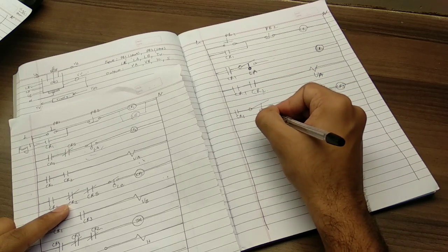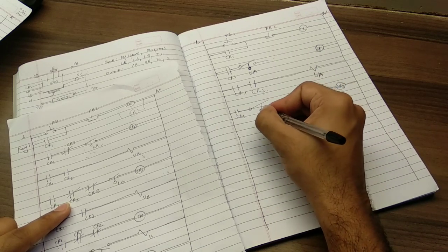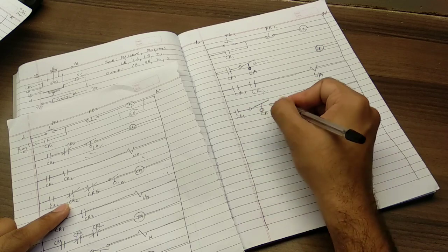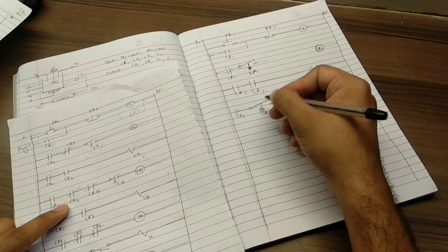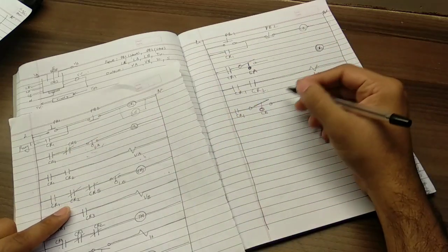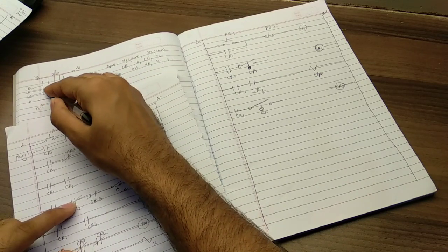Okay, LB. So this is again the float switch, and remember that this switch is above this point, so that means that once the liquid reaches the point, the switch will be open. Now another criteria in valve B is valve B should be actuated only when the solution has reached LA. So that means from LA to LB is basically the time when valve B is going to be on.